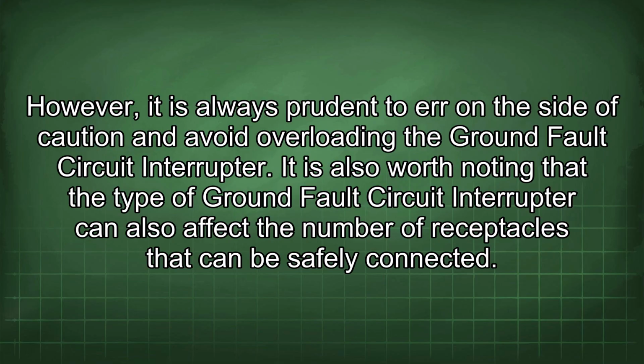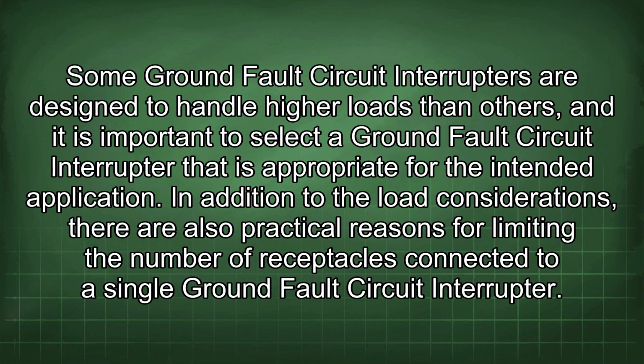It is also worth noting that the type of ground fault circuit interrupter can also affect the number of receptacles that can be safely connected. Some ground fault circuit interrupters are designed to handle higher loads than others, and it is important to select a ground fault circuit interrupter that is appropriate for the intended application. In addition to the load considerations, there are also practical reasons for limiting the number of receptacles connected to a single ground fault circuit interrupter.